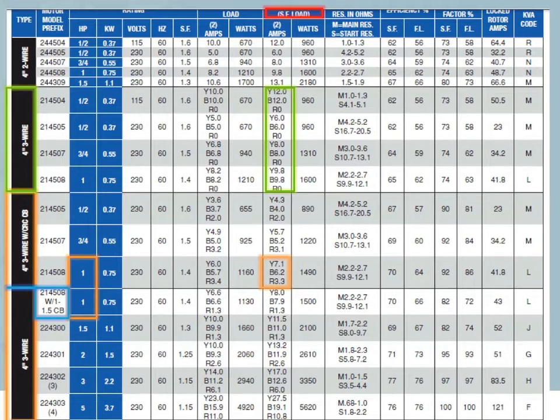You'll notice with the 1 horsepower control box, your max load amps are 7.1. With the 1.5 horse control box, your max load amps are 8. And so that's going to take a toll on the motor. You need to understand that. And you're looking at that yellow wire, which is your max load amps. Doesn't matter whether you're looking at this manual or whether you're looking at our manual, you want that yellow wire, which is max load amps. Your 2 horse there are 13.2, and that's why we set it for 13.5, so we can cover even the Franklin motor.